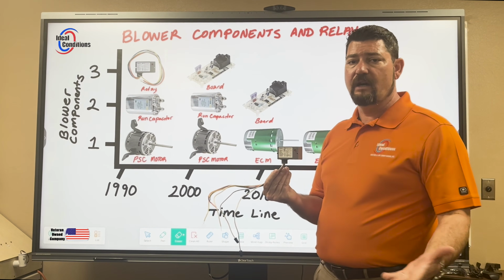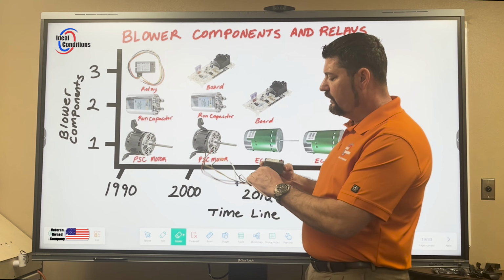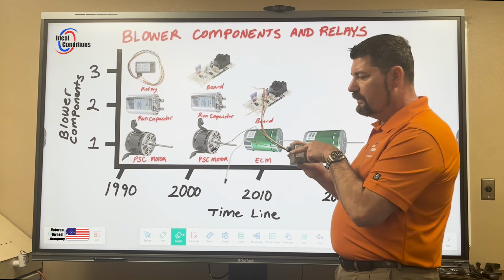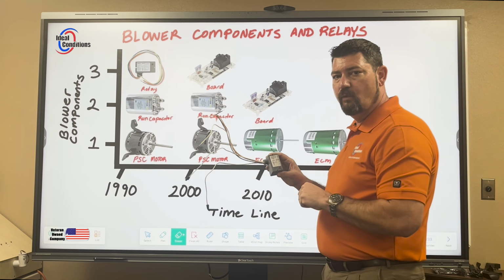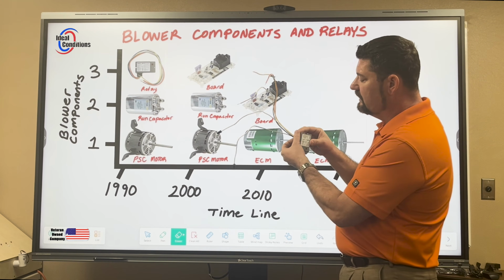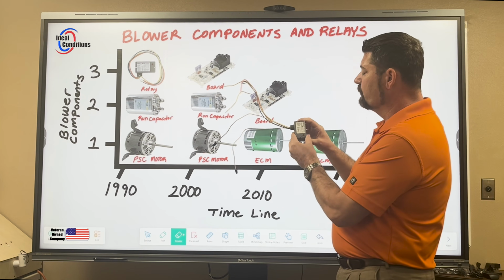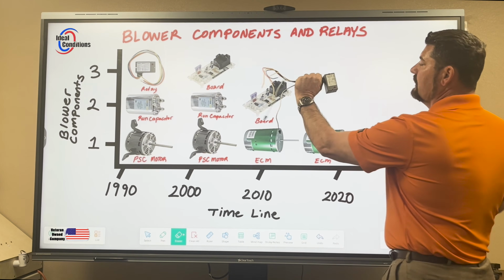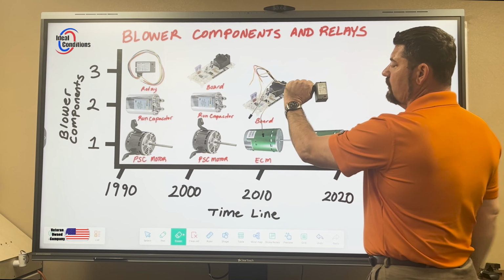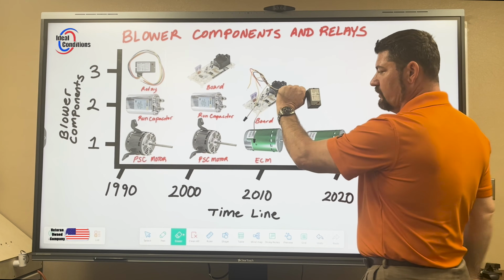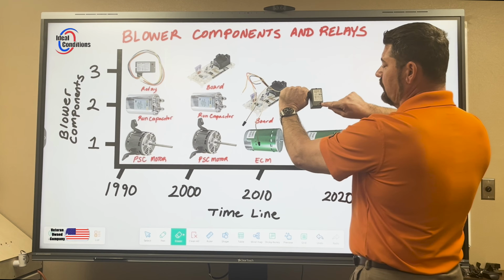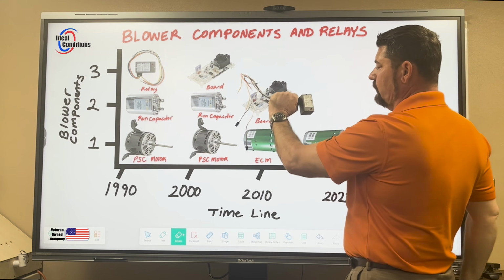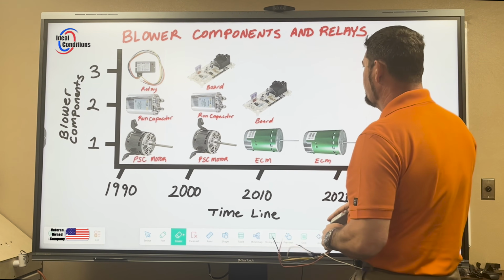It's perfectly fine. The nice thing about this relay too is, if you can see here, I can take a 3/4 inch knockout or just create one with my Unibit. I can slide this in there, put a lock washer on there, screw it on, and on the outside of my cabinet, that can be mounted there, and I know if I'm energizing my load by just coil voltage and that light's on. So pretty neat stuff there.